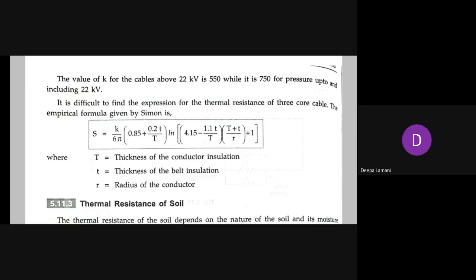It is difficult to derive the expression for thermal resistance of a three core cable analytically. The empirical formula given by scientist Simon is: S = (k/6π) · (0.85 + 0.2·t/T) · ln[4.15 - 1.1·(t/T)·((T+t)/r) + 1], where capital T is the thickness of conductor insulation, small t is the thickness of belt insulation, and small r is the radius of the conductor.